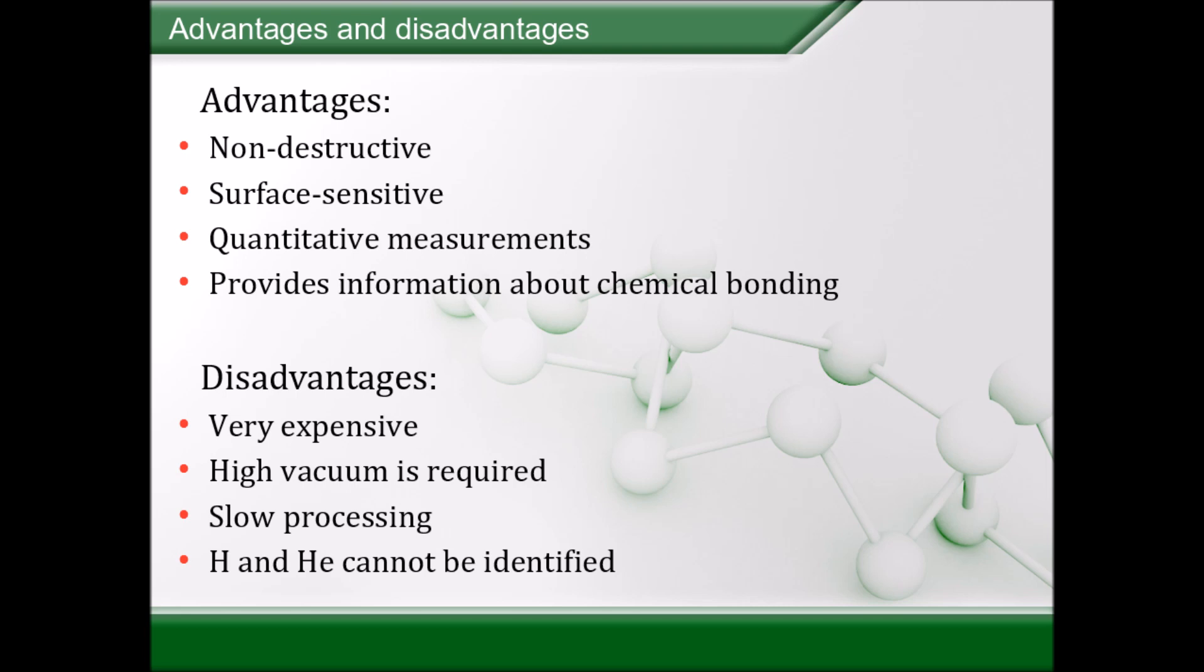On the other hand it has some disadvantages as well. It is first of all a very expensive technique. Secondly it needs a high vacuum and it is a slow process so it might need a whole night to provide results. And finally it detects all elements with an atomic number of 3 and above so it cannot easily detect hydrogen and helium.